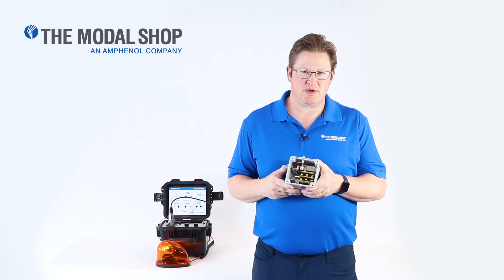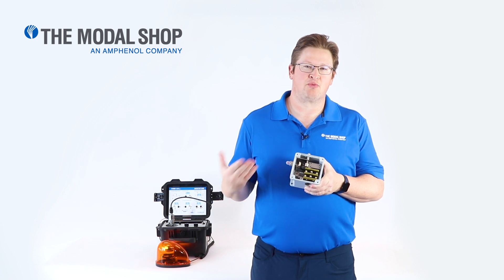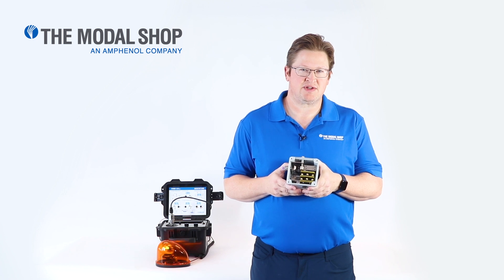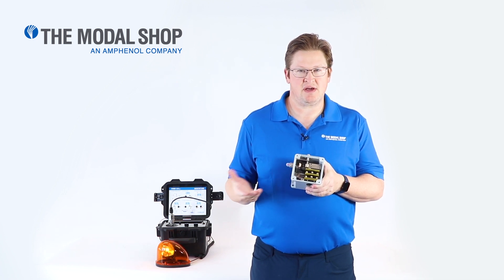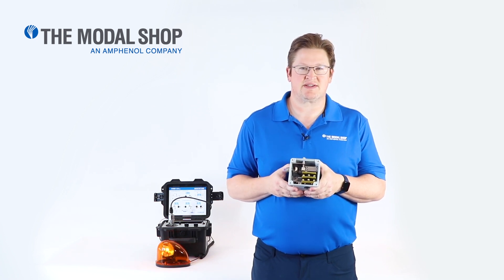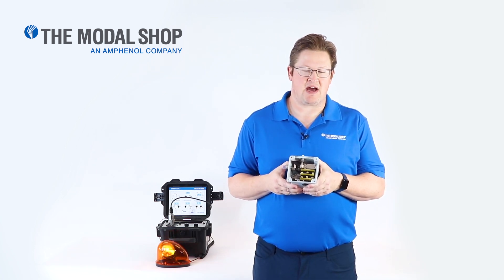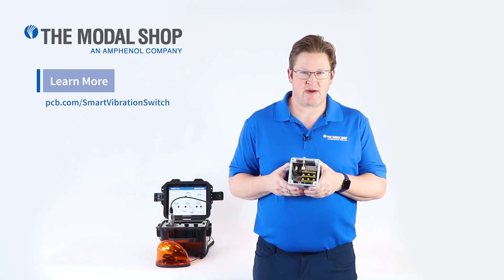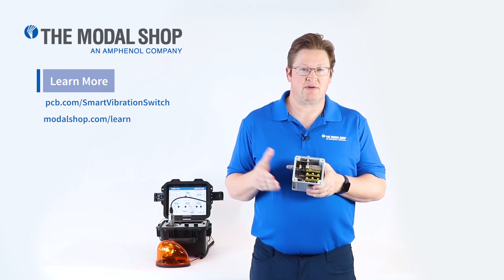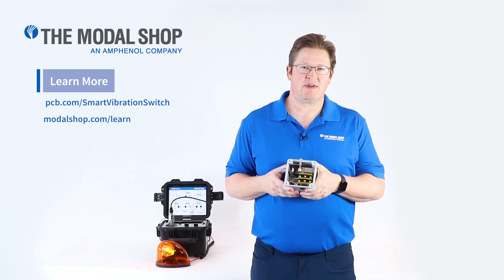Traditional mechanical vibration switches rely on a spring latch mechanism to trip — just like that. There's no precision with this device. The IMI Sensors 686 electronic vibration switch has an accelerometer built inside, and as you can see, we tripped at the exact vibration threshold level that we programmed. We were also able to create a 6-second time delay so that a transient vibration event or a temporary shock doesn't cause our machinery to shut down. For more information about the 686 vibration switch, check out the PCB Piezotronics website. And for more information about the Model 9100D Portable Vibration Shaker Table, check out the Modal Shop website and our learning portal. Thanks for watching.